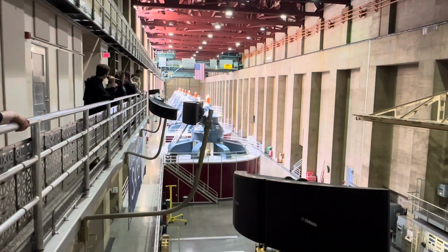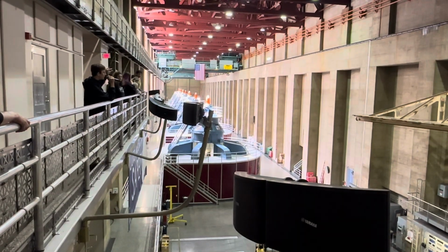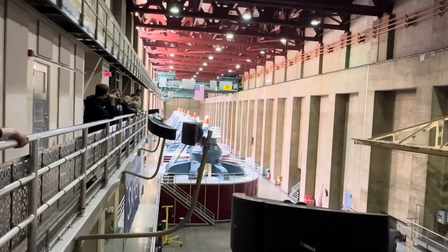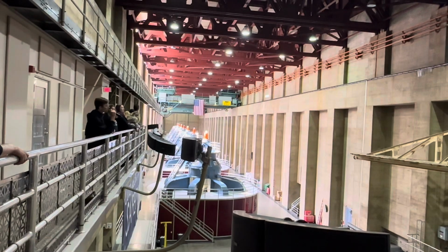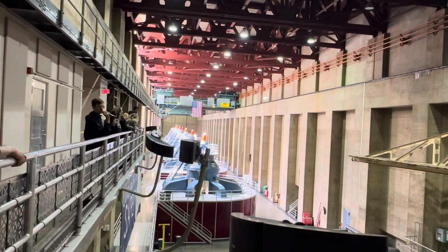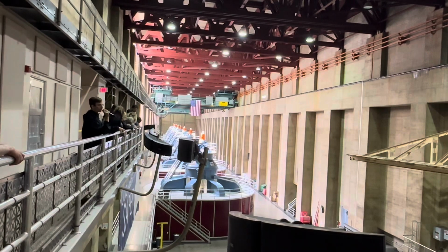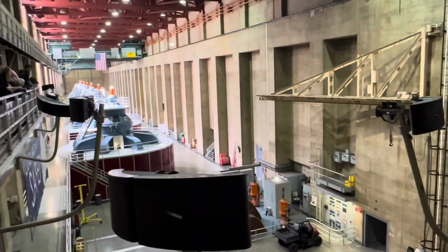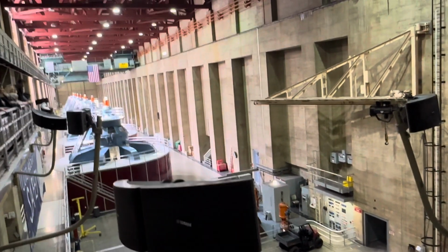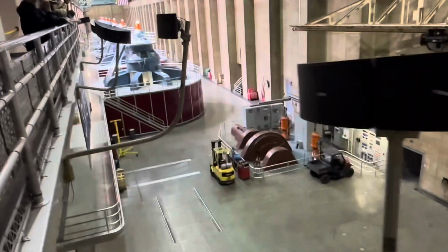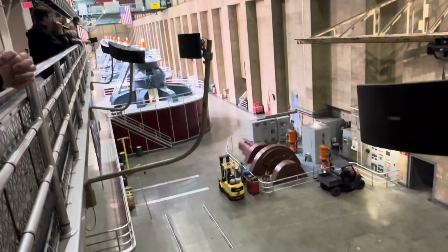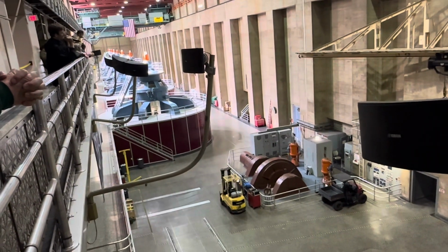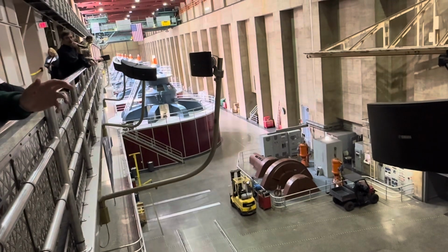As we look down the wing, it is only the generators with the indicator light on top of them lit up that are actually operational. So this would be generator N1 and N7. Inside those 2 generators, the rotors are spinning around at 3 revolutions per second. Now, if we look down, we'll be able to see one more indicator light lit as well. This would be generator N0. So the rust-colored generator that's kind of on its side, sticking halfway out of the ground, that is also operational. This is one of 2 of our Pelton water wheels. We have another one in the Arizona wing. Each of these makes 2.4 megawatts, and that power stays here and is used at the Hoover Dam.